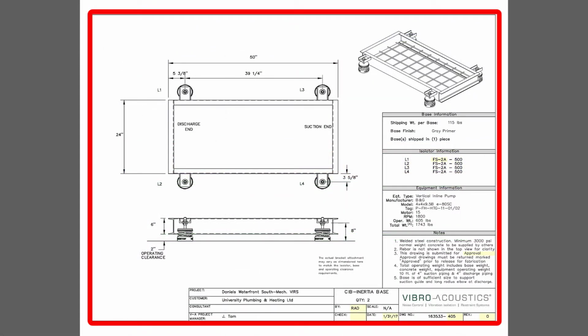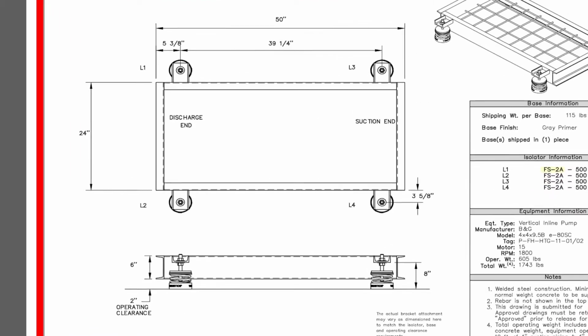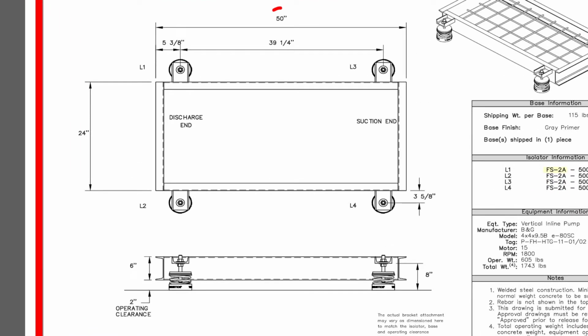Every concrete inertia base is made to order. They can be made any size to match the specifications and the supported equipment. Our submittals document their sizes and important dimensions for installation. These are all things we can easily check on a job site. Here we see that the base for each heating water pump is 50 inches long, 24 inches wide, and 6 inches deep.